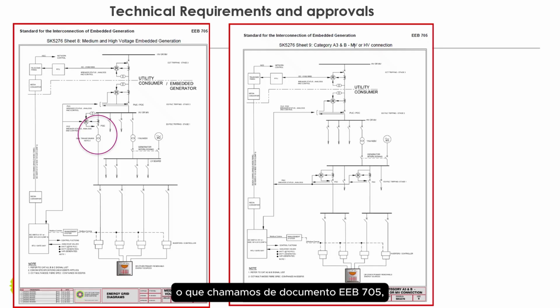So we have what we call an EEB 705 document, which is the standard for the interconnection of embedded generation for medium voltage and high voltage. And we've got standard diagrams here depicting how these SSEG can be connected to our network. The red circle there indicates the one option, where it is done via a generator transformer. The other one next to it is without a generator transformer, using the customer transformer where the SSEG is embedded into the LV network. Both are acceptable.